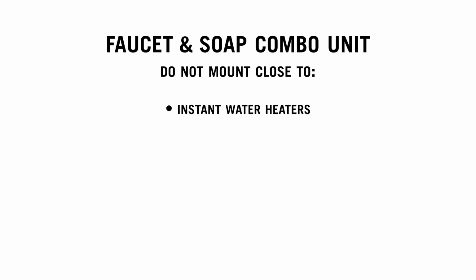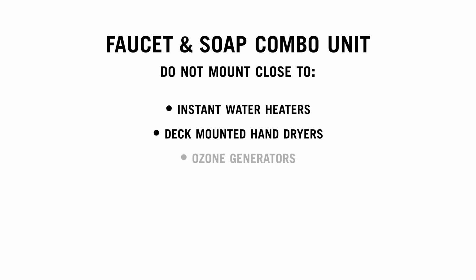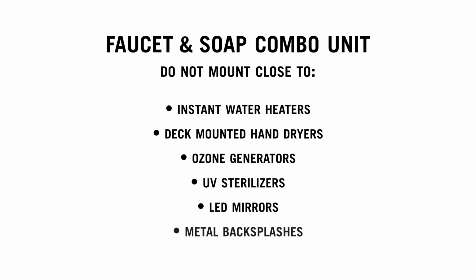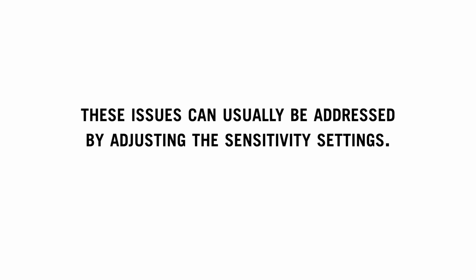The third check is the location of the faucet and soap dispenser combo unit. They should not be mounted near any sources of electrical noise. This can cause interference with the capacitance field. Don't mount close to instant water heaters, deck-mounted hand dryers, ozone generators, UV sterilizers, LED mirrors, or metal backsplashes, etc. These issues can be addressed usually by adjusting the sensitivity settings. If you have any questions about what can cause interference and how to resolve it, you can always contact Delta Commercial Technical Support for assistance.